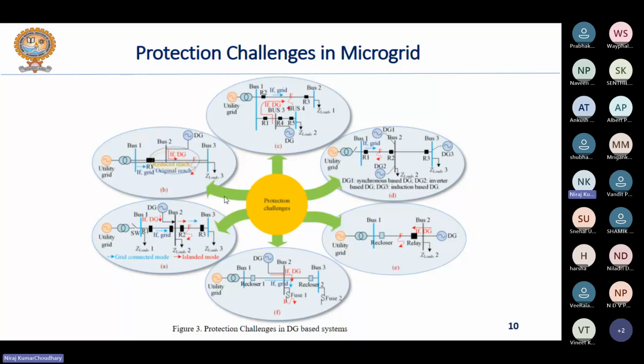Before we go into the detail of the relay coordination problem, you should know what coordination means, right? On the occurrence of a fault, there should be a particular sequence of operation among the different protective devices in the system. This is a very basic part, but let me recall once again: suppose you have a system and a fault occurs in that system, then there are different layers of protection. So the very first layer is provided by the recloser, if present in the system.